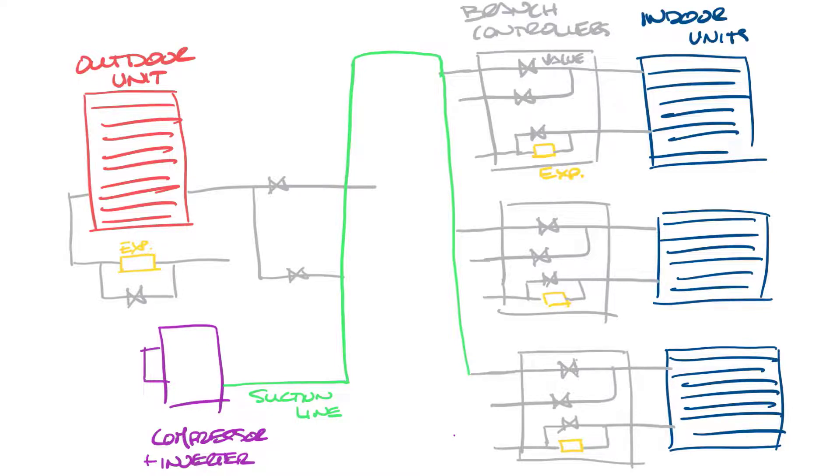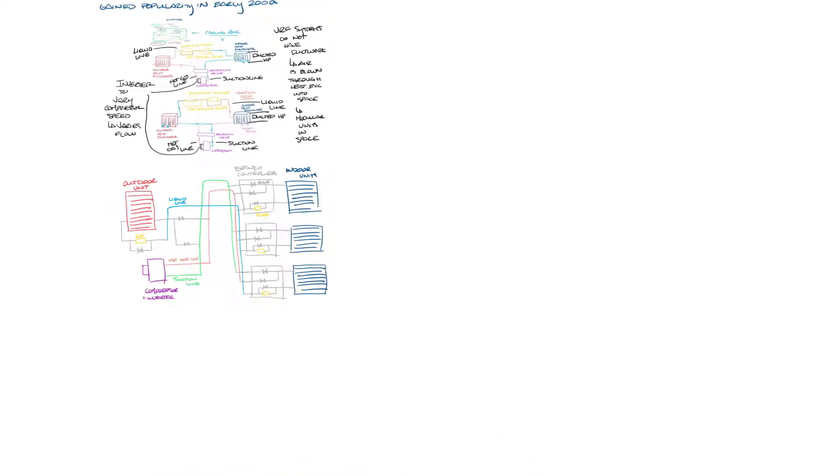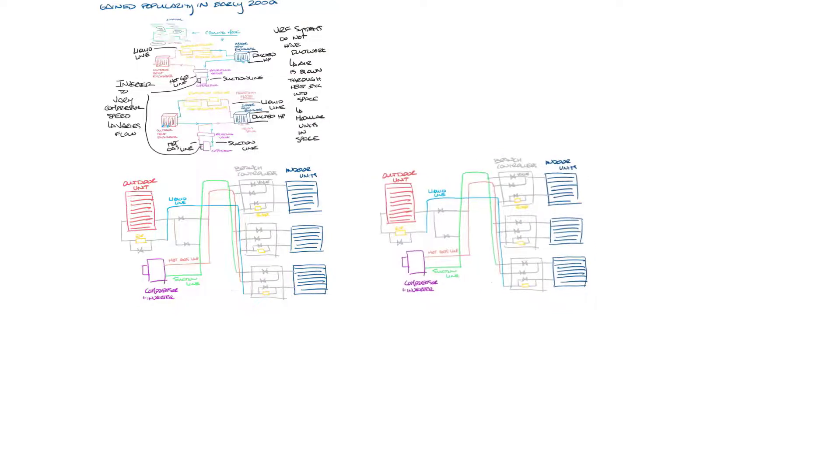Now the second line in the branch controllers, this is the hot gas line. This is going to come out of the compressor. It's also going to connect to the outdoor unit. And then these last three lines are the liquid line and it's going to connect over here to the expansion device. So since that took some time to draw let me make two copies of it to talk about later.